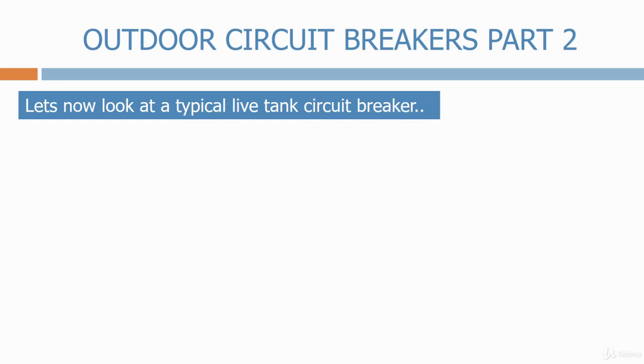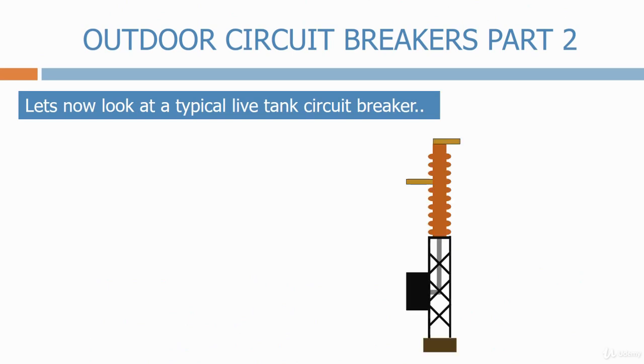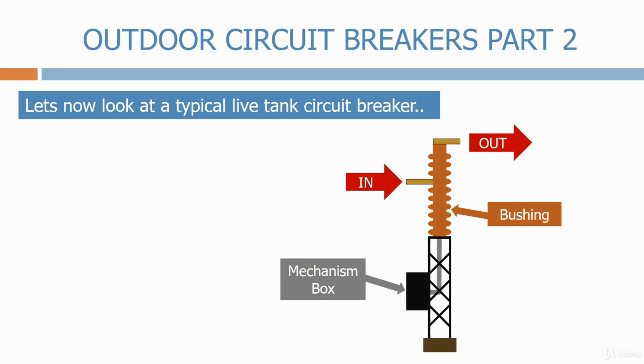Let's now look at a typical live tank circuit breaker. These are very different to the dead tank circuit breakers. Firstly, we have the input terminal and the output terminal. We have the vertical bushings, which contain the circuit breaker contacts. And finally, the mechanism box, which contains all the open and closed circuits and mechanical linkages to operate the circuit breaker.